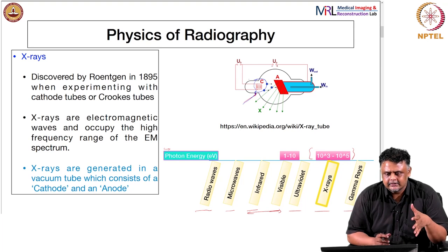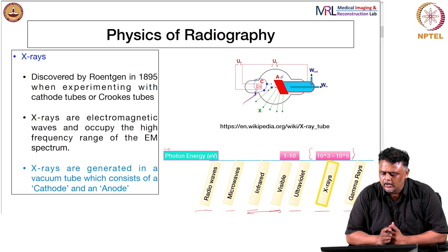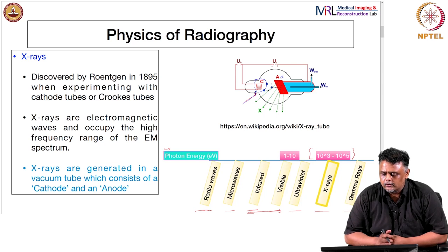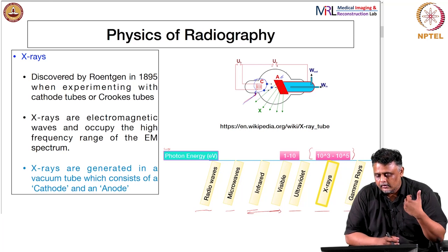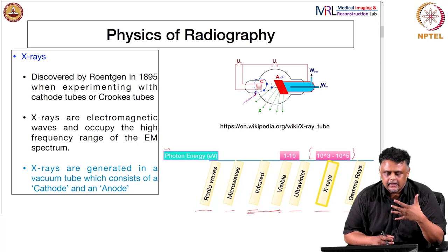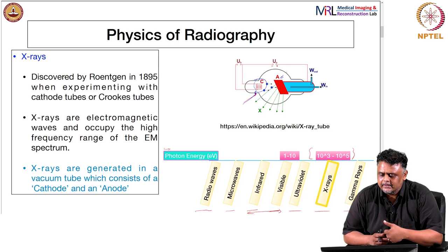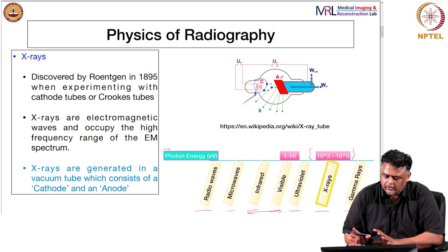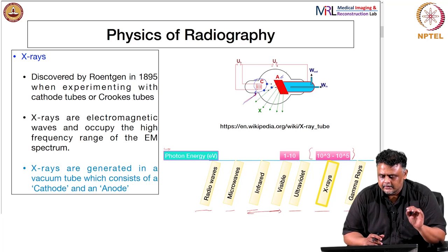These electrons are accelerated by a potential difference across the tube to strike the anode target, which is typically coated with tungsten or other high-Z materials. As electrons hit the anode target, they penetrate it and emit energy in several forms. The electrons are absorbed by the anode, and the process results in the emission of x-rays. Modern tubes have various modifications for more efficient imaging, but this is the basic construction of an x-ray tube.